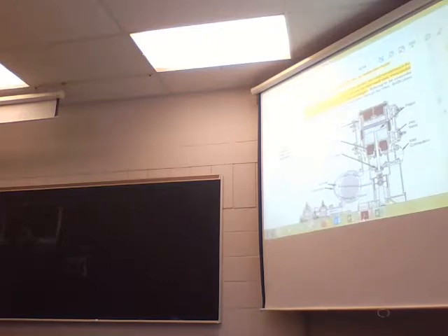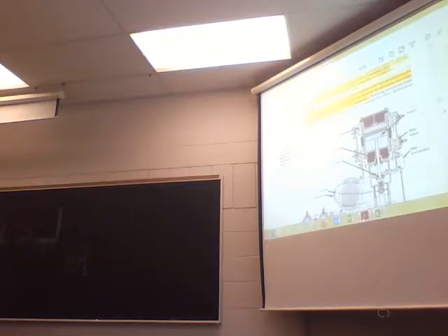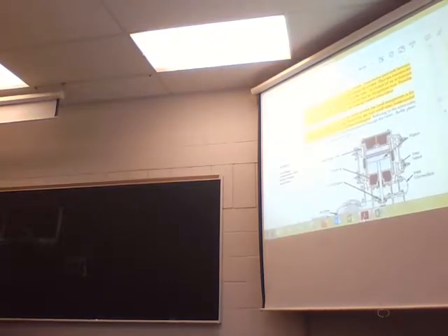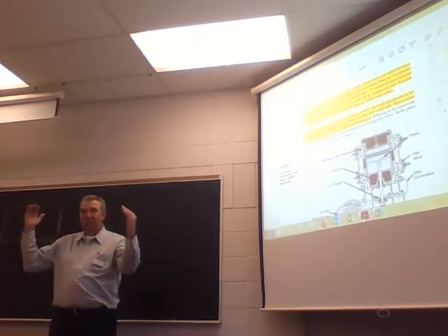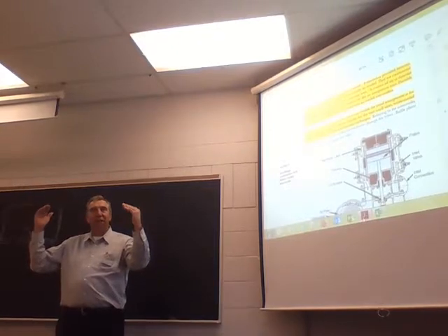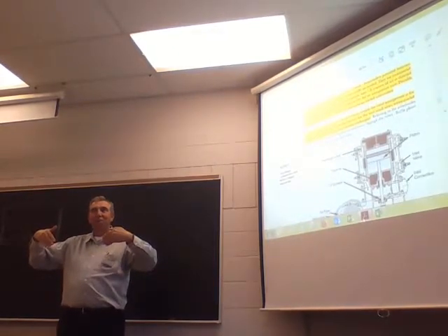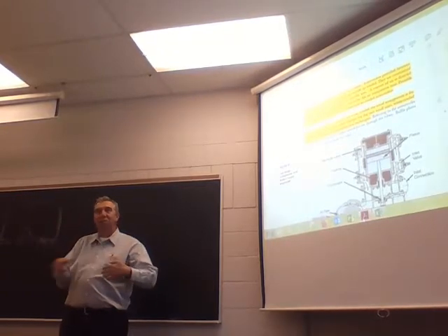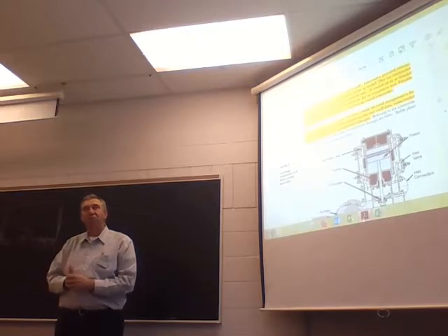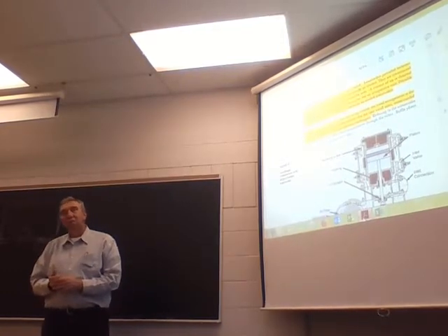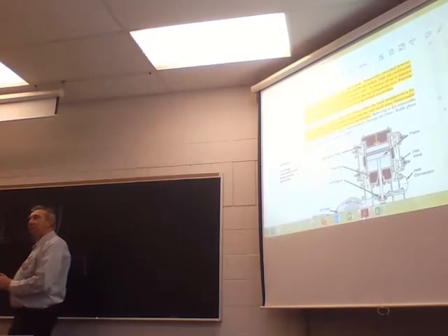You guys remember taking that air compressor in the lab apart, the one that's cut in half? You can see it. Remember that big flywheel that was on it? You notice the fan blades were on it? So not only did it act as a driving pulley, but it also had fans on it, so when it turns by the electric motor, it actually draws the air across the cooling fin to the intercooler. Most compressors are done that way.